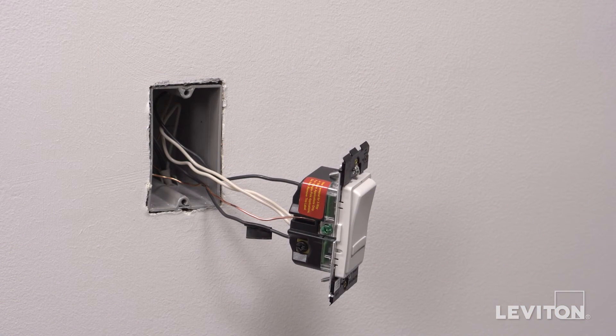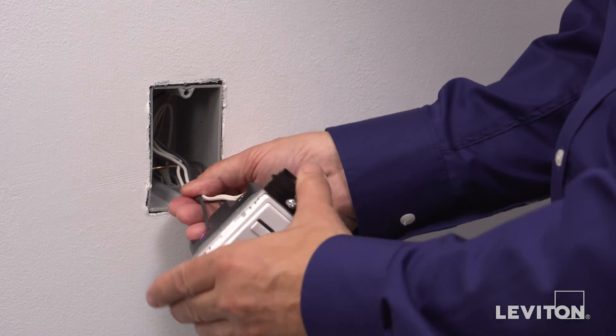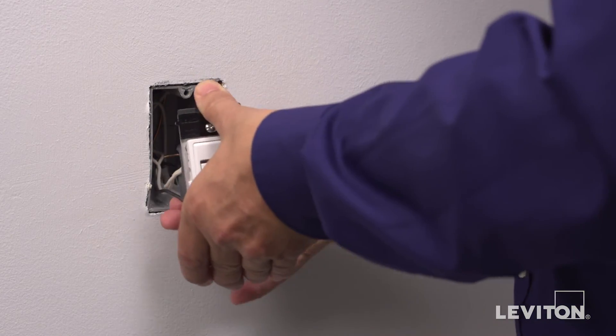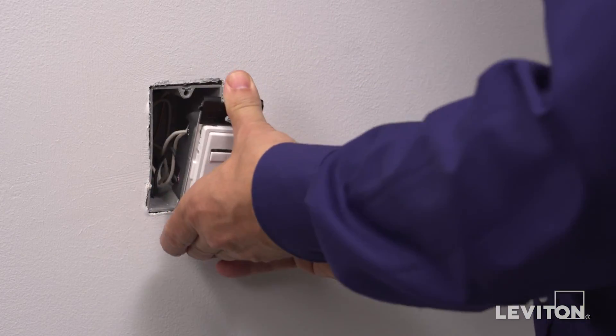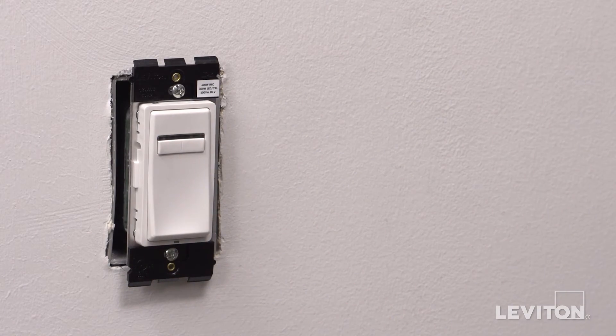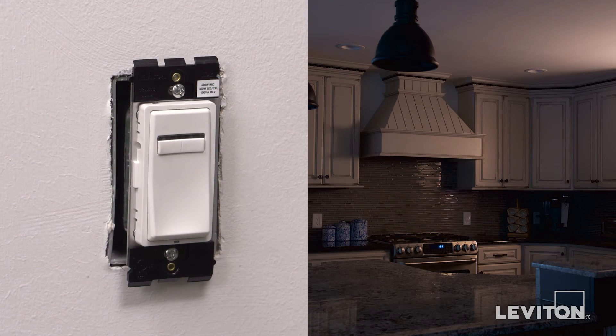Now that everything is wired, we'll test the device prior to fully mounting in the wallbox. Gently bend the wires and push them into the wallbox. Partially screw in the mounting screws in the wallbox mounting holes. Restore power at the circuit breaker. The status light on the device will turn white.